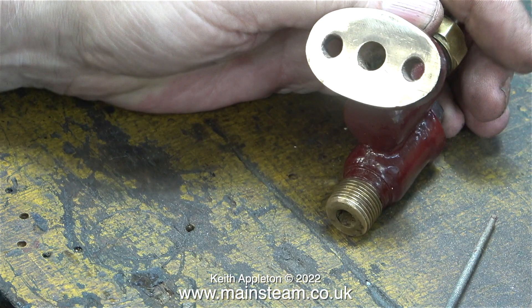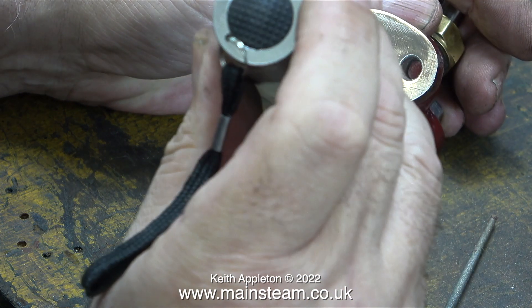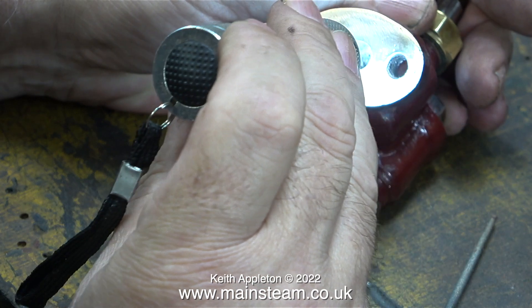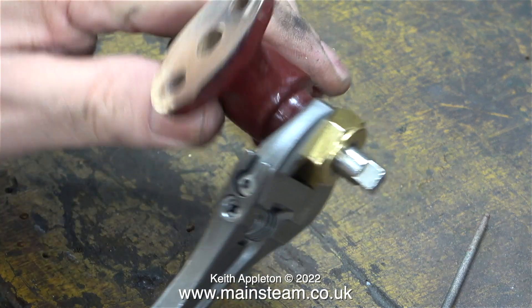Before refitting this check valve I will of course make a new gasket. And this time, thanks to Hermetite, I was able to remove the old gasket material cleanly, so when I refit the check valve with the new gasket I won't need to use any sealant at all. In this shot I'm actually trying to show down inside the valve, where there is clearly quite a large step between the centre rotary part of the shutoff valve and the casting. By using a torch I can clearly see this step, but I can't capture it with the camera — more about this later.